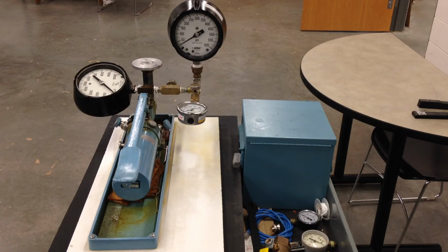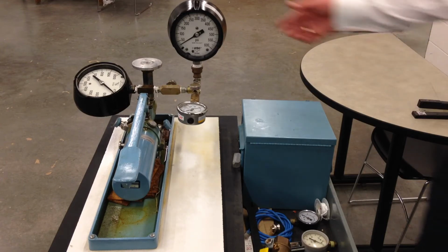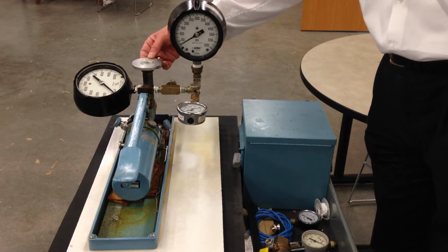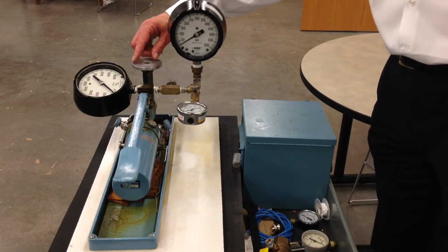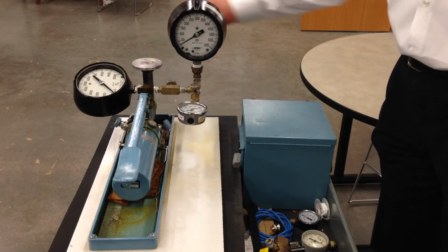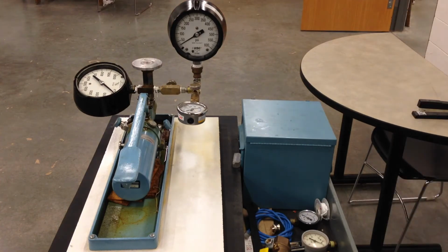They're pressurized by this. This is the dead weight pressure gauge. What we're going to do is put weights on this thing, and those weights create a dead weight pressure, and that's going to pressurize the system. Then we compare the dead weight, which is our reference, to the actual pressures we get out of the gauges. Obviously the dead weight is the reference, and these are what it's reporting. Your question is, how accurate are they? You're about to find out.